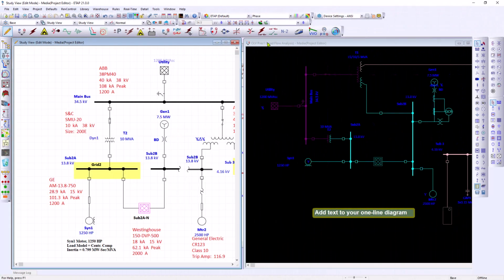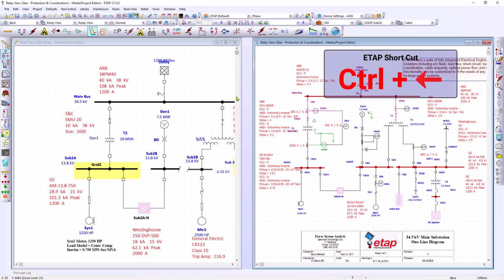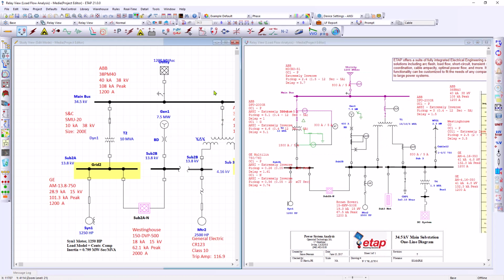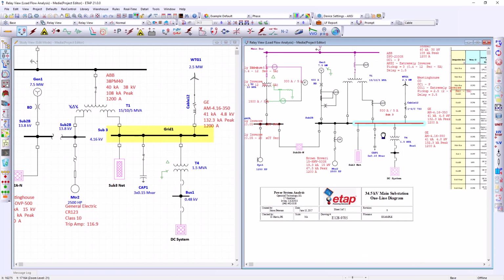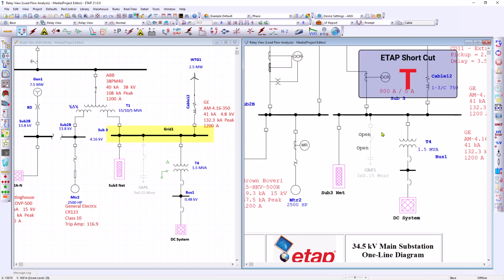Next, I'm going to use these two presentations to do a quick what if analysis. So I have these two side by side. I'm going to run a load flow and I'm going to compare these two projects, one with the capacitor on and the other off. And one of the keyboard shortcuts I like to use in this case is T. So when you use T, you can open a breaker or open a switch. And all you do is toggle with T back and forth. I highlight the equipment, I hit T and it closes. So that's a quick one for me.